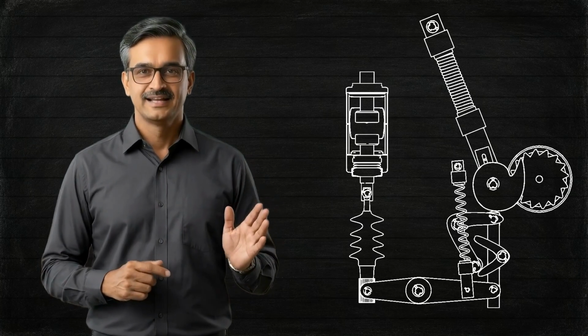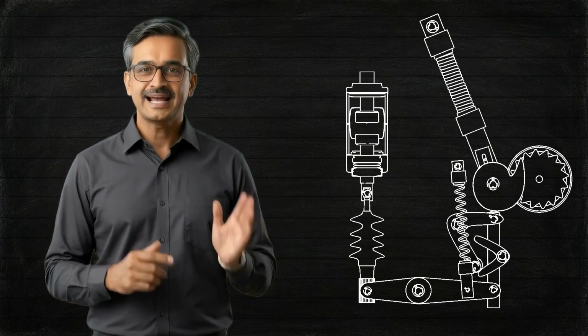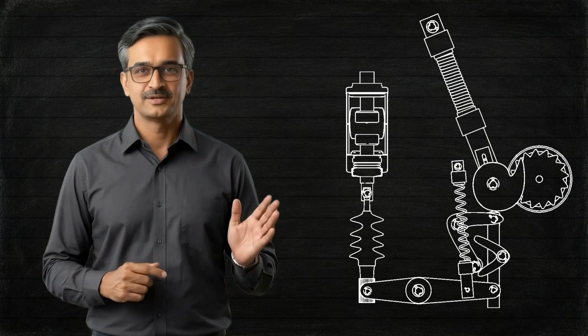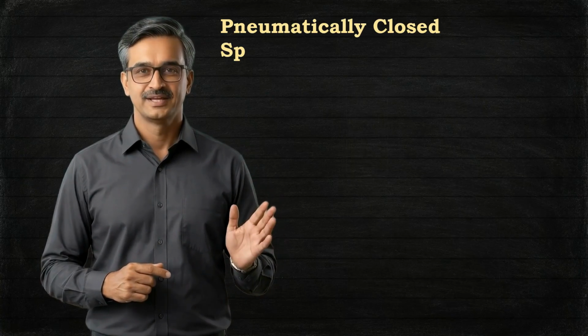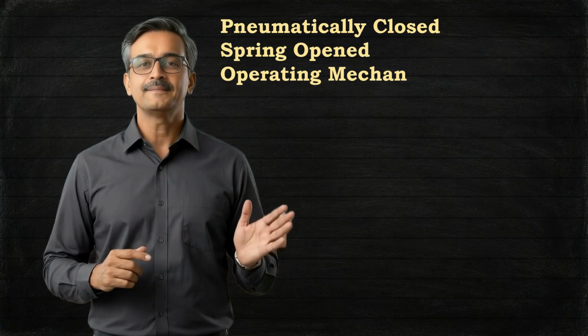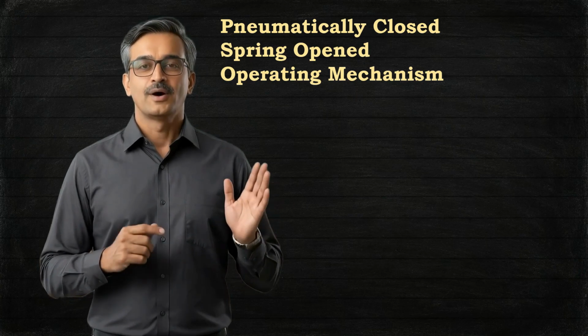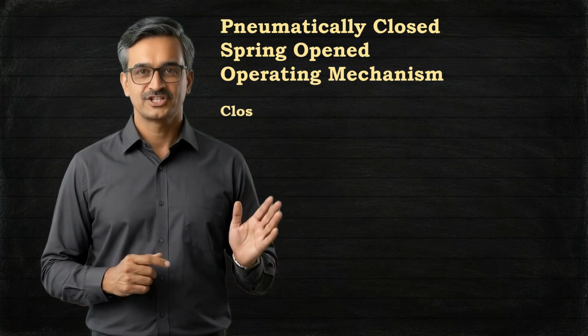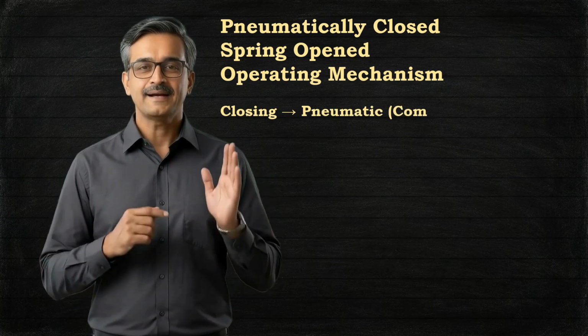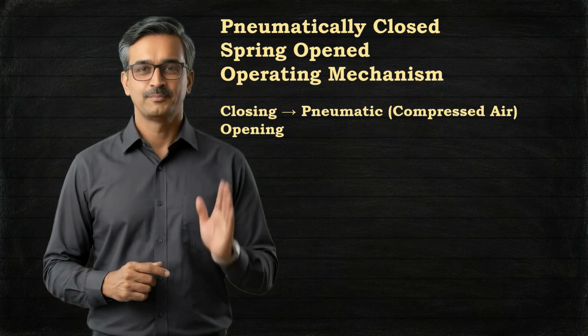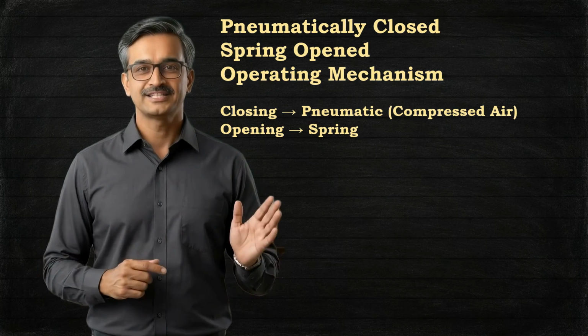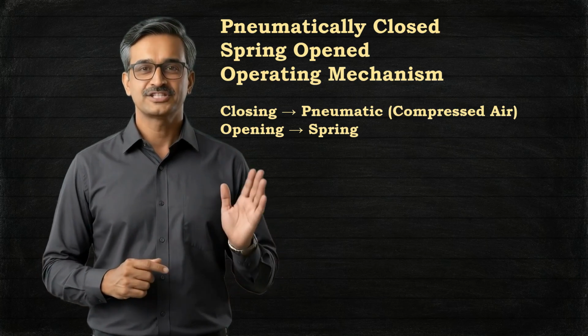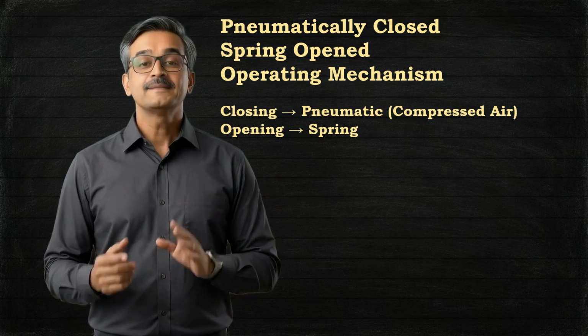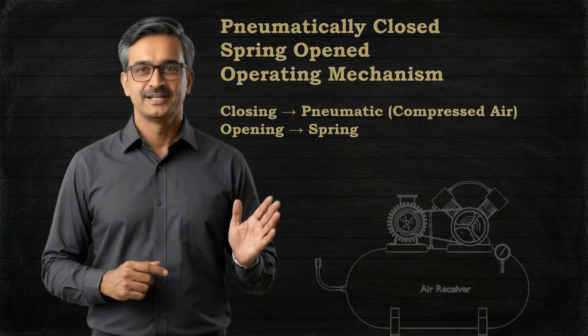Now let's discuss another important operating mechanism used in extra high voltage minimum oil circuit breakers and also in some SF6 circuit breakers. Pneumatically closed spring-opened operating mechanism. The name itself tells us how it works. Here, the closing operation is carried out by compressed air, while the opening operation is performed by a spring. That is why it is called the pneumatically closed spring-opened mechanism. Now let me show the complete arrangement.